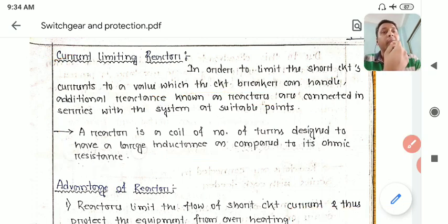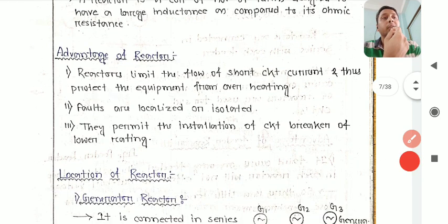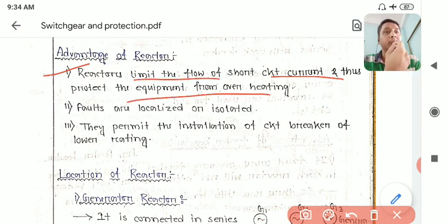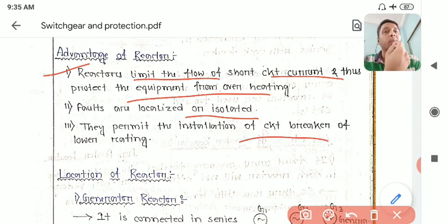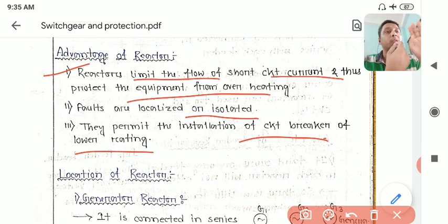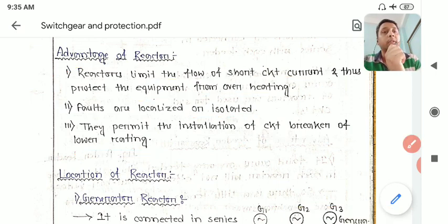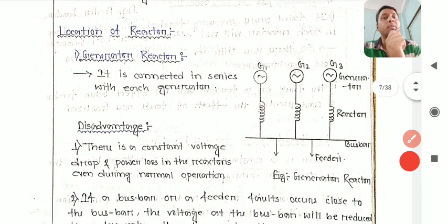The advantages of fault limiting reactors are: the fault current can be limited to protect equipment from overheating, faults are localized or isolated, and they permit the installation of circuit breakers of lower rating. If you can reduce the fault current, you can use a lower-rated circuit breaker.